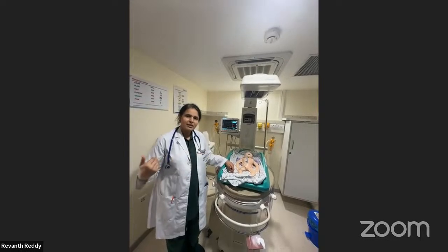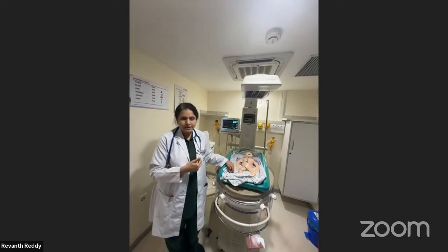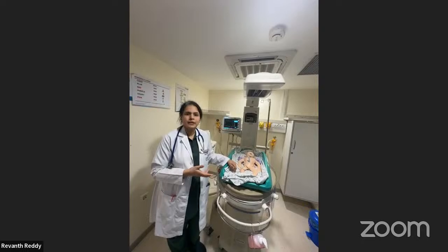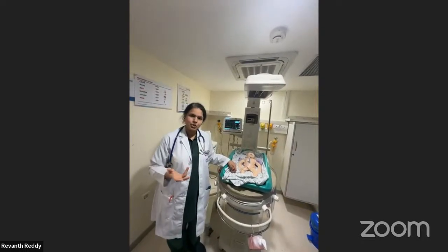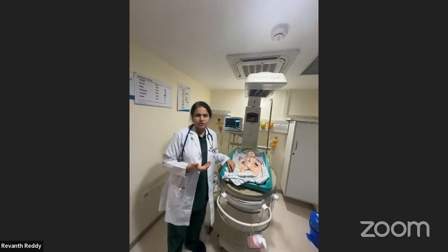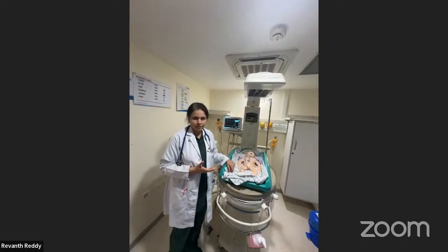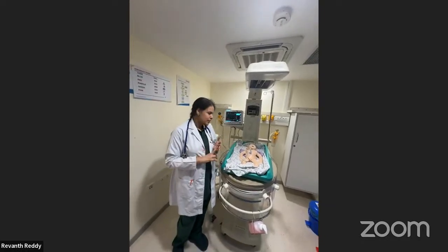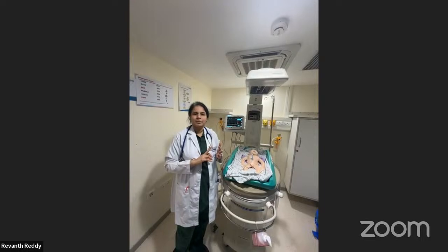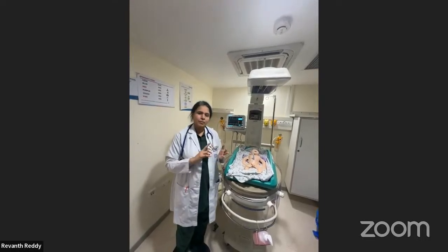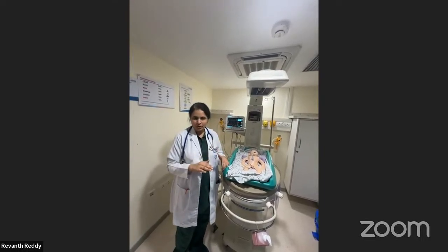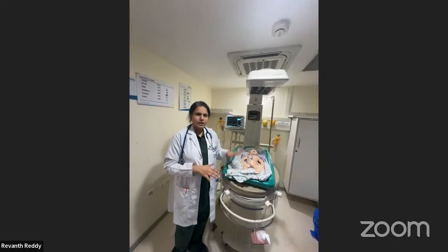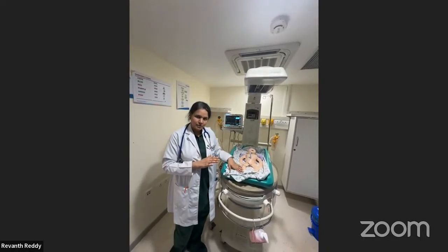One should not immediately remove the FS29 mattress at any point of time, because this can result in rapid fluctuations of the baby's temperature and it can lead to abrupt rewarming, which is also unfavorable to the baby. So during Mira Cradle, the troubleshooting will be more intense. Nursing care will be more intense because this is not servo controlled. This is completely manual. It relies on the phase changing mattress technology.